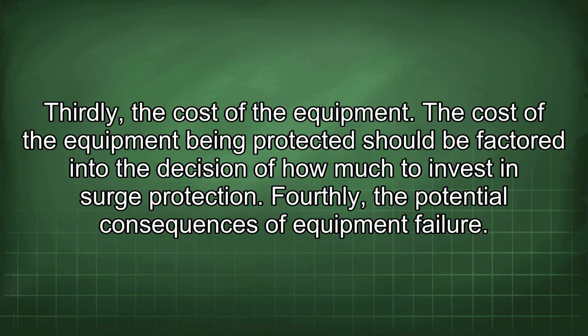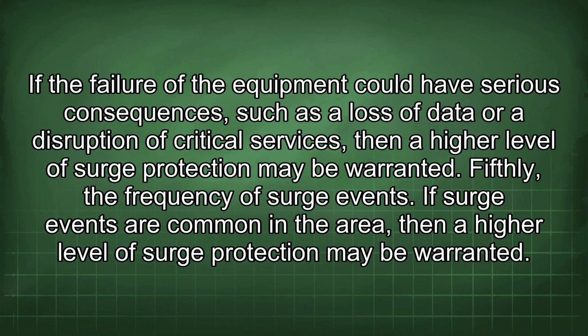The cost of the equipment being protected should be factored into the decision of how much to invest in surge protection. Fourthly, the potential consequences of equipment failure. If the failure of the equipment could have serious consequences, such as a loss of data or a disruption of critical services, then a higher level of surge protection may be warranted. Fifthly, the frequency of surge events. If surge events are common in the area, then a higher level of surge protection may be warranted.